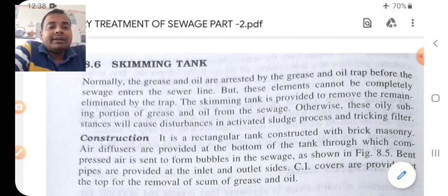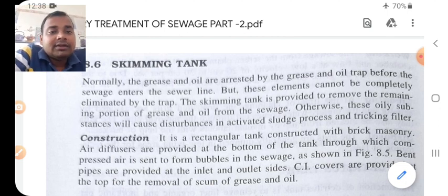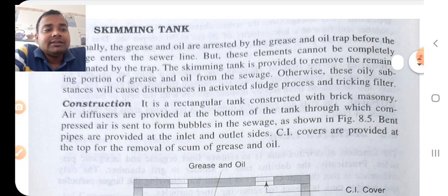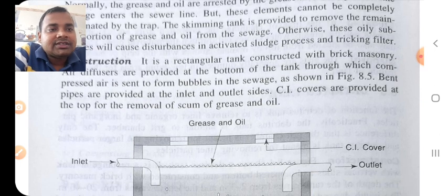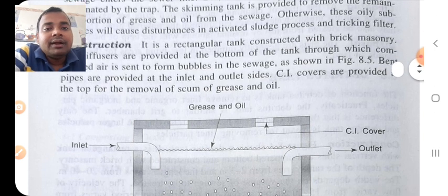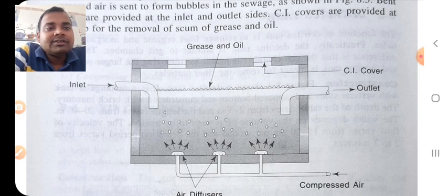The sewage oil and grease-type material is trapped in the grease and oil trap before the sewage enters the sewage line. Otherwise, the oily substances will cause disturbance in the activated sludge process and trickling filter. Construction: it is a rectangular tank constructed with brick masonry. Air diffusion is provided at the bottom of the tank through which compressed air is sent to form bubbles. Bent pipes are provided at the inlet and outlet sides, and CI covers are provided for removal of scum of grease and oil.